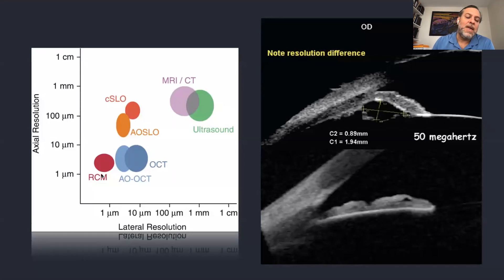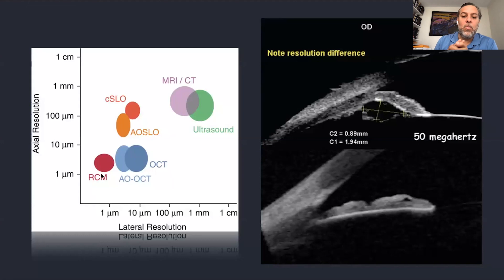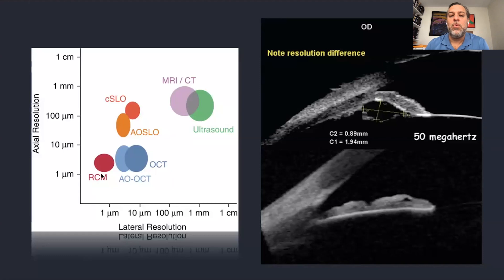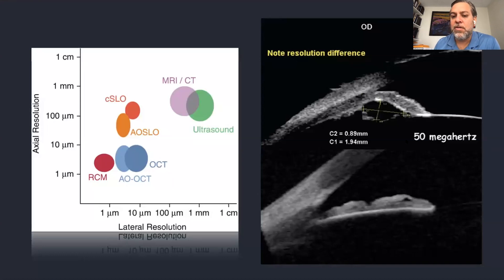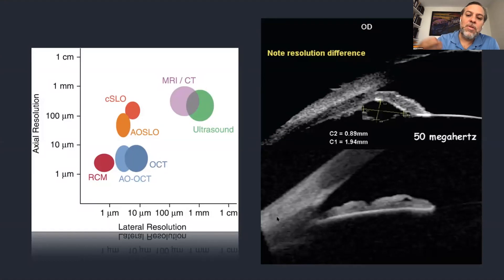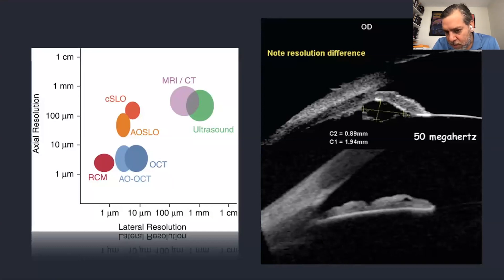Resolution comes hand in hand with acquisition speed — better resolution takes more time. Comparing anterior segment UBM with a 50 MHz probe versus OCT imaging, OCT provides better resolution, though ultrasound has greater penetration depth, allowing visualization of the iris and ciliary body in locations where regular OCTs cannot reach.